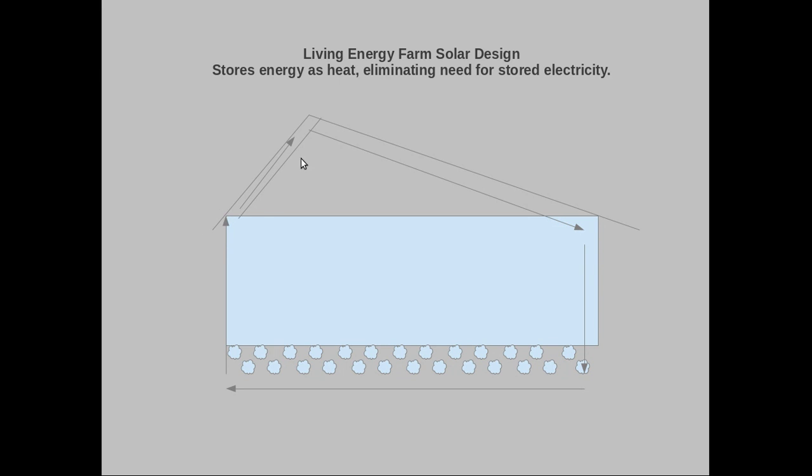The southern roof has foam behind the sheet metal and then a metal roof. Glass in front of that collects heat. We pull that heat down through a duct system right under the floor and back up and around it goes. The blowers are hot wired straight into the 180-volt solar rack. So the sun comes out, blowers turn on, sun goes down, blowers turn off. No controls, no problem.